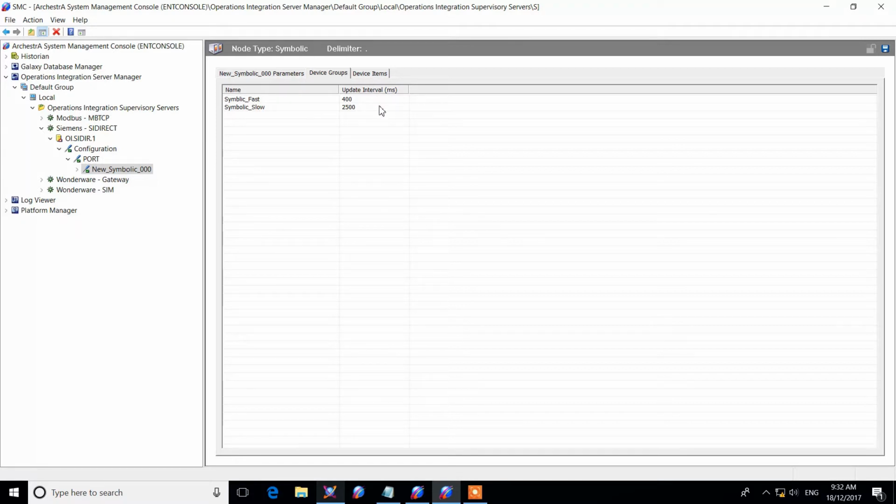I would suggest, however, that if you're going to make user interactions, anything over about 0.3 of a second is going to feel clunky. So assign things that are going to require user input to relatively fast scanning rates. Otherwise the users will feel, even if the overall system is very responsive, that their interactions with it are slow, and it will make the system feel poor. Just a sort of a UI kind of hint there.